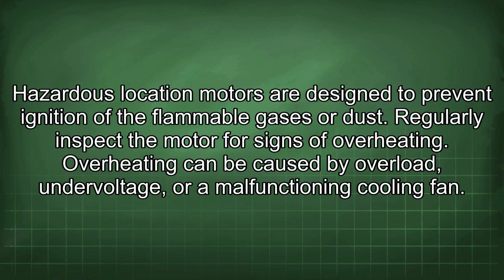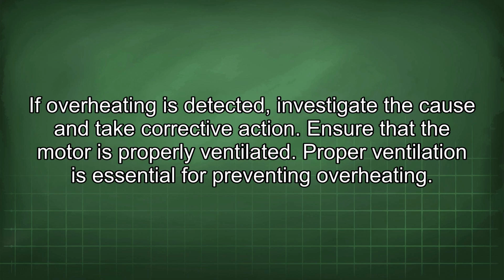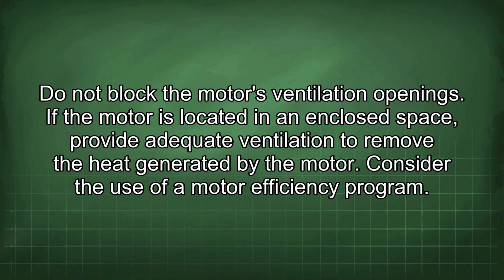Regularly inspect the motor for signs of overheating. Overheating can be caused by overload, undervoltage, or a malfunctioning cooling fan. If overheating is detected, investigate the cause and take corrective action. Ensure that the motor is properly ventilated. Proper ventilation is essential for preventing overheating. Do not block the motor's ventilation openings. If the motor is located in an enclosed space, provide adequate ventilation to remove the heat generated by the motor.